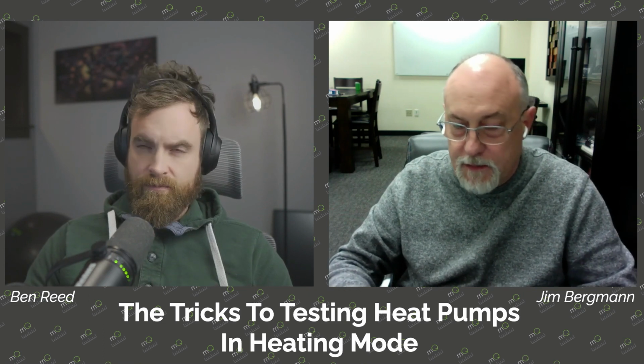Let's talk about what we can do in the heating mode with a heat pump. Let's talk about the two interconnecting lines, because it's important for mapping. On an air conditioner, we have a liquid line and a suction line, right? Because they only have one function, the liquid line feeds liquid to the indoor TXV, and then you have a vapor line that takes the vapor back to the condensing unit outdoors.